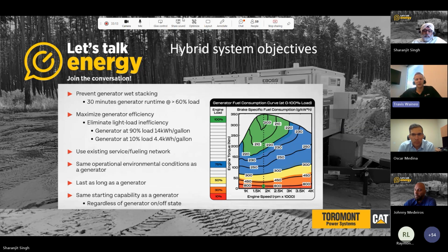And then last, as long as a generator. We want to make sure that the hybrid system or the battery system is going to last years and years, especially when we talk about the generator runtime reduction, like we will in some of the case studies. We want to consider how many fewer hours there are on that generator. We want to make sure those assets have a similar lifetime at least, so we don't have to replace the batteries every few years while that generator doesn't have a lot of hours. So there are lifetime considerations. And then starting capability, you just want to make sure that if you could start something with a 70 kVA generator, you could start the same piece of gear with a 70 kVA hybrid.